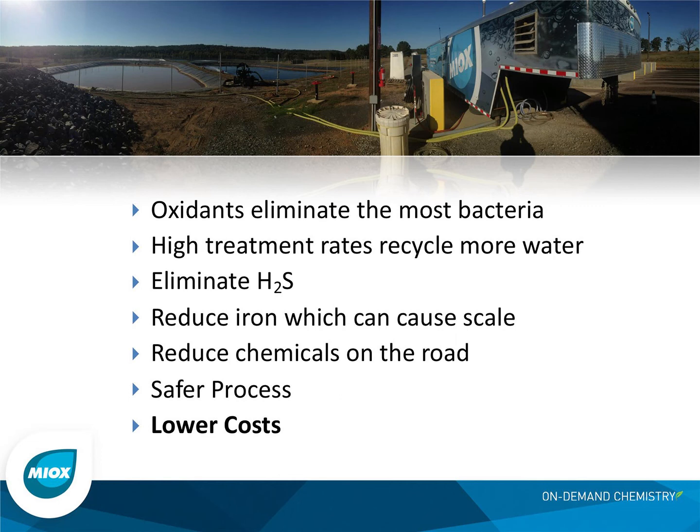All right, the first question I hear is, can you confirm if your system can be adapted or modified to produce mixed oxidants from brackish water, around 3,500 milligrams per liter, which is 80% sodium chloride and the remaining 20% sulfates? We've done some tests under 10,000 milligrams per liter that we've seen positive results with, but 3,500 is probably a little low for us to actually generate using that, but we could supplement with salt if we had to. We can definitely supplement with salt to get that oxidant up. An ideal number would probably be in that 20 to 30,000 milligram per liter range.